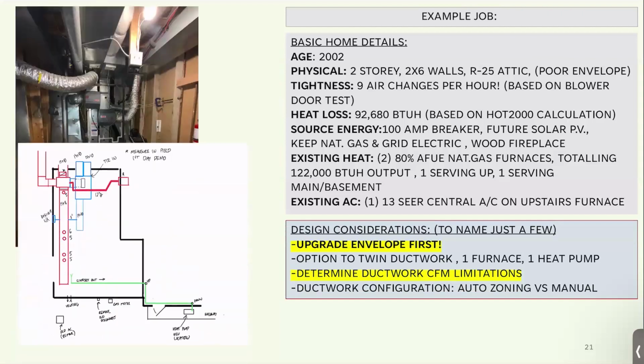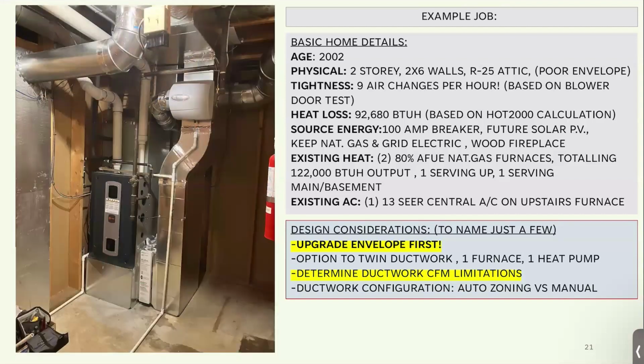So this is ultimately what we chose to do. I had to make a drawing to understand it in my own mind, and the clients, and in the installer's mind. And so a few things you had to take a look at was space. It doesn't take up any more footprint. In fact, it's less footprint than the 2, obviously. We just have to figure out how we tie it all together. So it's a challenge. It's not easy. Ultimately, that's what it came out and looked like. We had to put more airflow at the bottom of the furnace. We just couldn't get enough, so we put it on a stand.